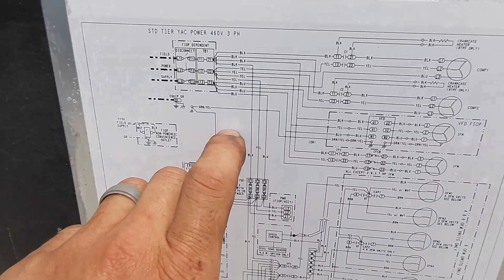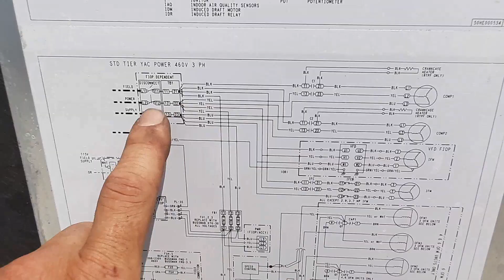I gotta look at a diagram again. I don't see anything here. I'm gonna work my way back down, do the same thing on that end, and then we'll pop these back in and make sure everything's secured, but I don't think anything's shorted out in here. You can usually tell pretty quick. So crankcase heaters aren't gonna be in play. There's my crankcase heater there. They're fed from the compressor contactors, which come directly from the power feed.